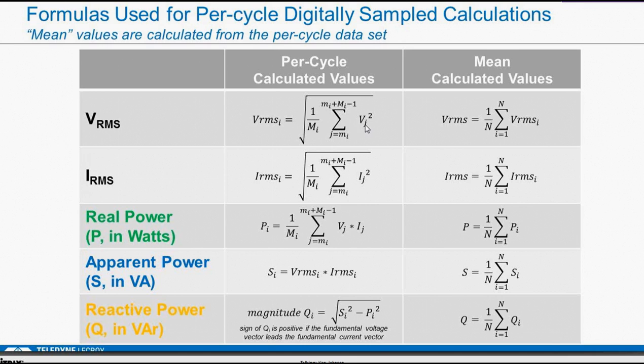J is the individual samples, and so the RMS value is the square root of the voltage value squared. This just says take only those points that are within that period and divide this summation over the total number of points. And that's how we calculate the RMS for a given cycle. Then if we have 10 cycles, we have 10 RMS calculations, and we calculate a mean value. We do the same for the current, and then we calculate the real power just by multiplying point by point the values.